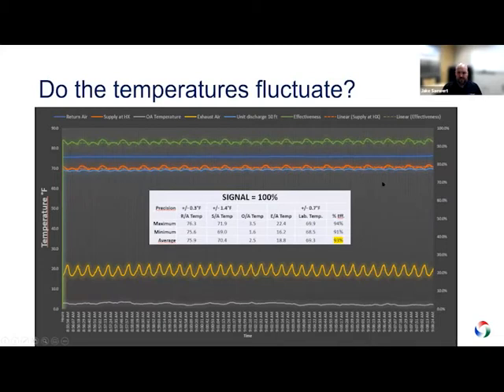sample of an output from a test that the ACCUBLOC manufacturers ran. You can see at the bottom here, this is actually in yellow, that is exhaust air temperatures. That has the widest band of fluctuation, but it's still only a couple different degrees. The supply heat exchanger, the most important one, is a much smaller band, and you can see that the temperature in the orange, the solid orange line, is taken right after the heat exchanger. If we get 10 feet downstream, it smooths itself out quite a bit. And remember, this is going to be included in a unit that's going to have heating and fans in it. So you're going to essentially mix it inside the unit by the time it gets to the discharge.